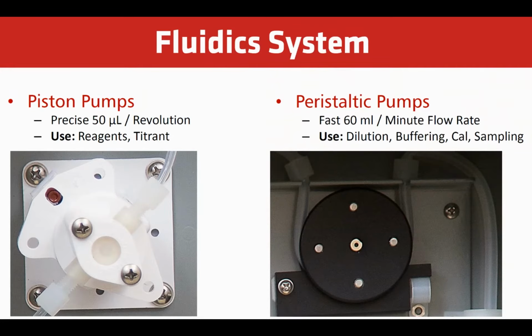Peristaltic pumps are much faster, with much higher flow rates. We use these for dilutions, buffers, to inject calibration or actually samples into the reaction cup. So these are used where critical finite amounts of liquids are not required.